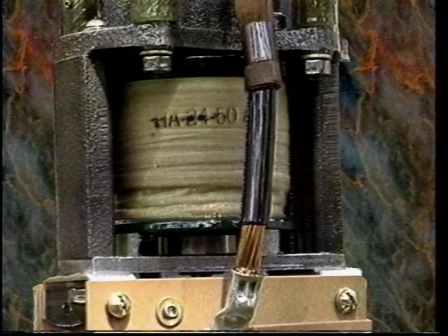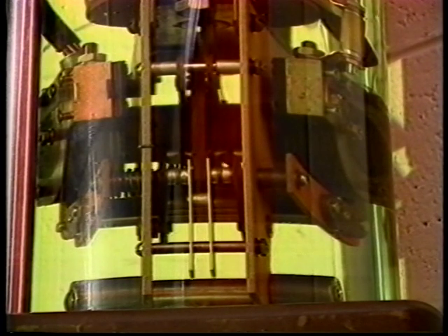Operation. When an overcurrent of sufficient magnitude flows through the trip coil, the tripping action is initiated and the contacts are opened. The recloser contacts then reclose following a predetermined length of time. By the time the recloser has reclosed the circuit, the sequence control device has moved to count the trip operation. If the fault still persists on the circuit when the recloser closes, the tripping and reclosing sequence is repeated a predetermined number of times as established by the sequence control device until the recloser goes to lockout.